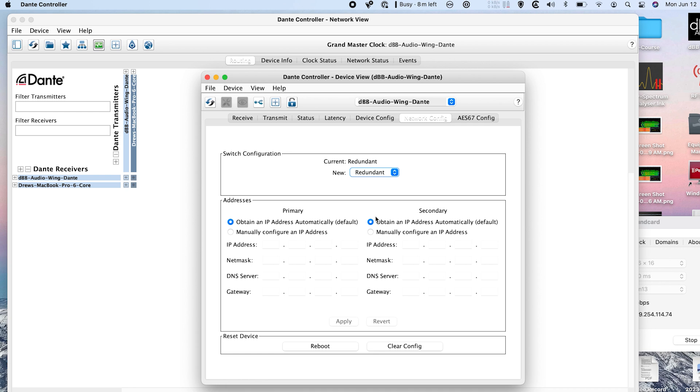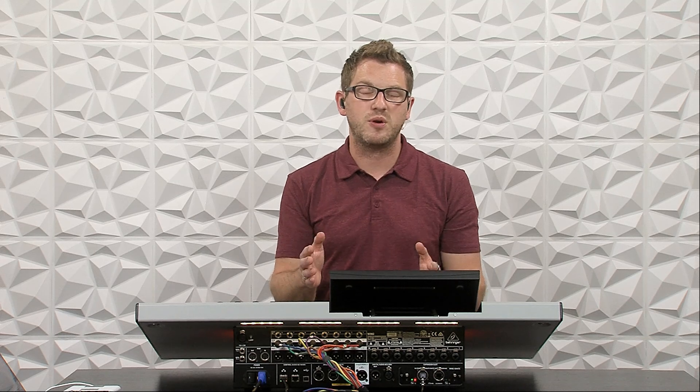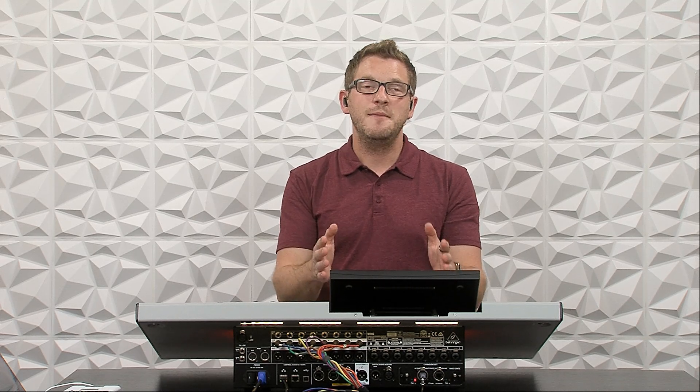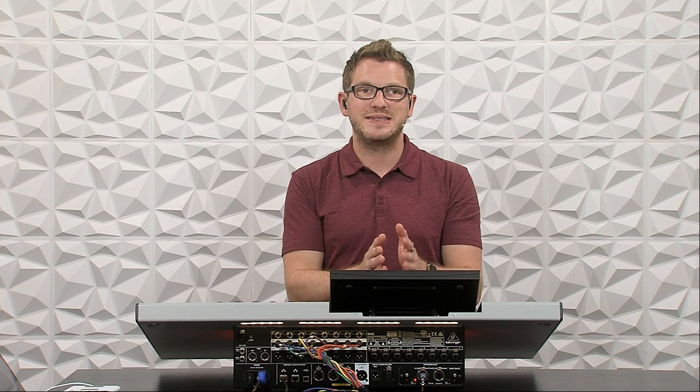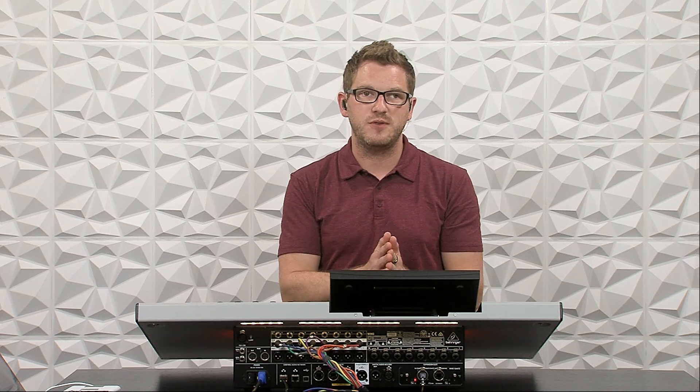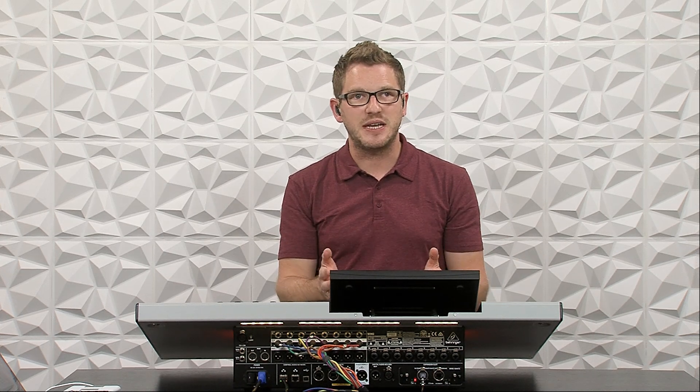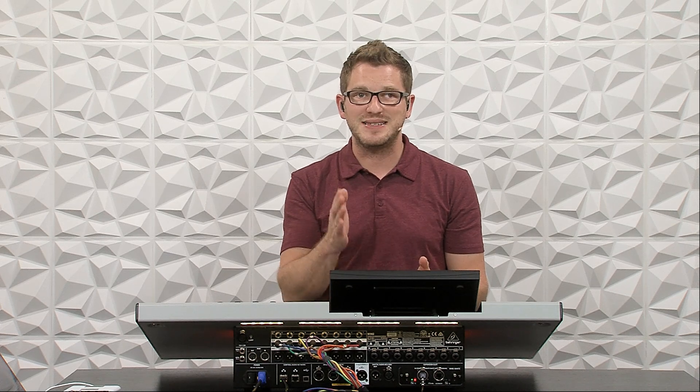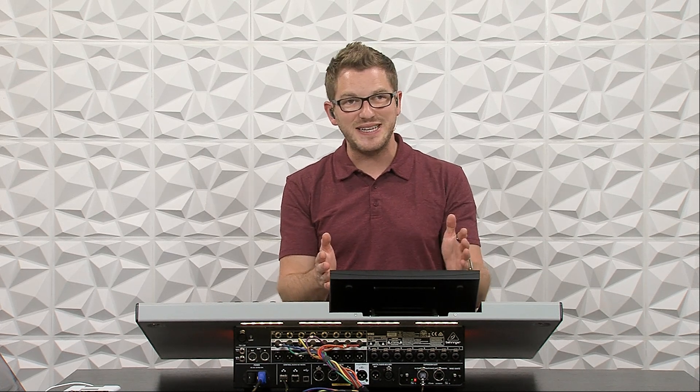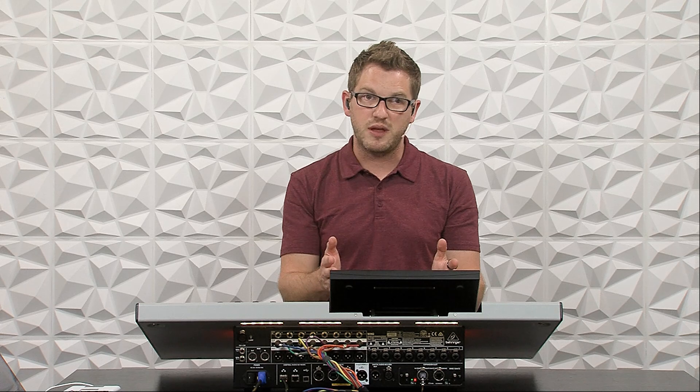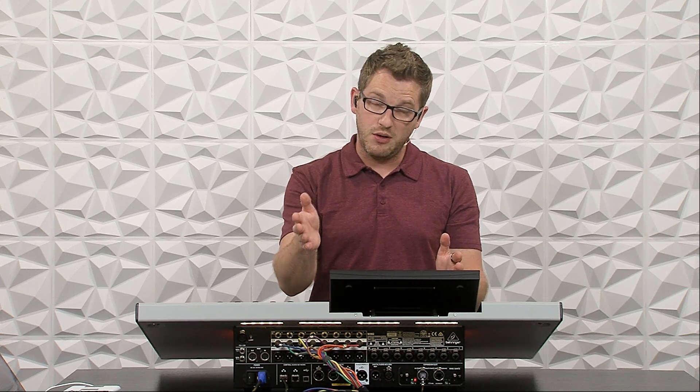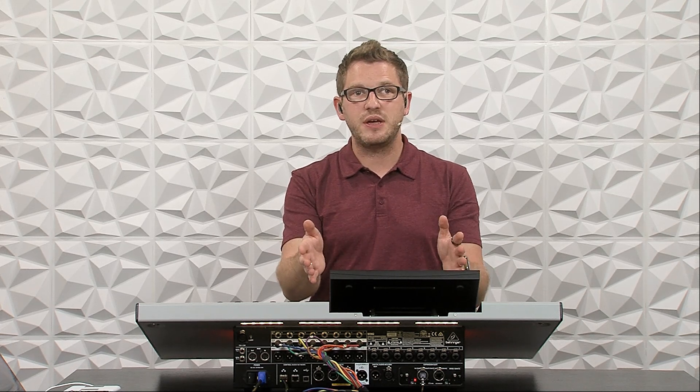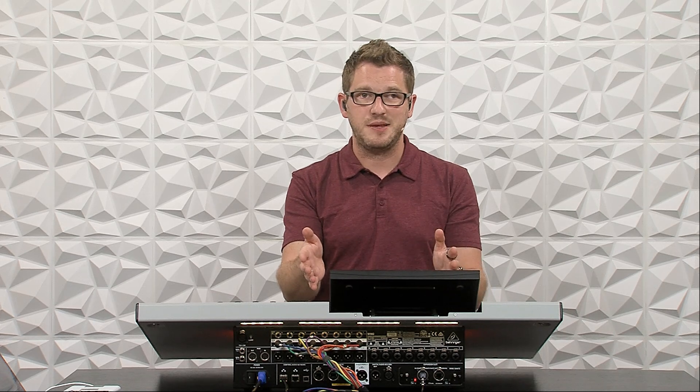Now this card can either be set to a switched mode, which means that the primary and the secondary port will talk together, and so you can extend more devices off of that secondary port if you wish. In a redundant setup, it uses the primary as the primary network and the secondary as a redundant network. And that way if the primary dies, then the secondary network would pick up immediately.